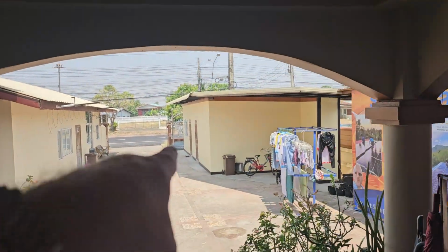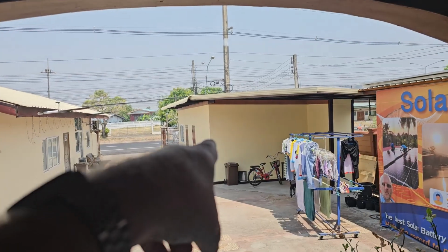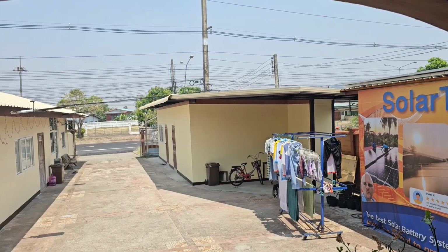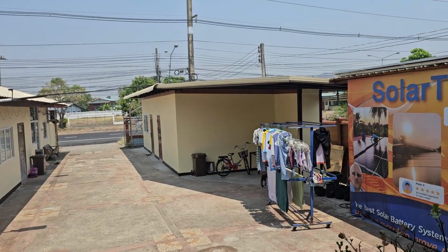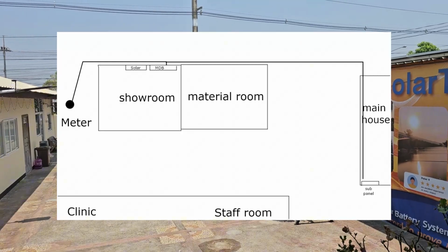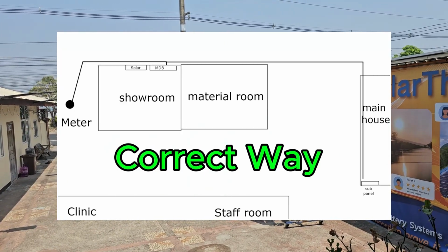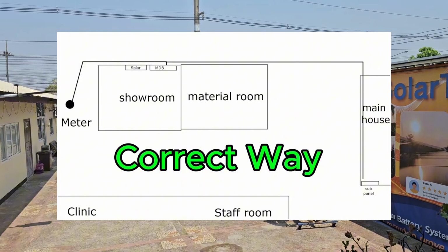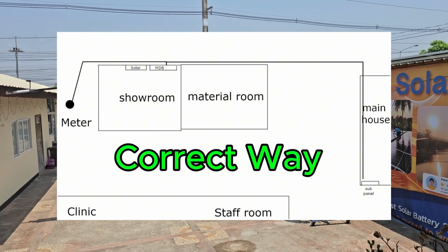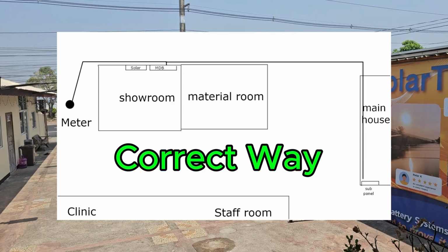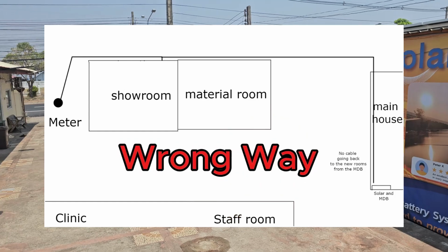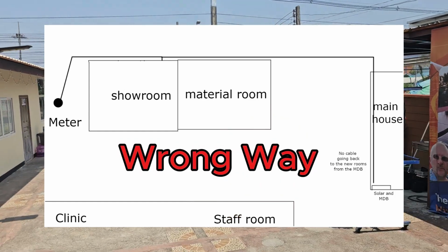have the solar system in the first room and then measure the electricity at that point, which means that it's measuring all the power going into all the rooms, because it's measuring at the first point. That's the whole key. Okay? So I'll show how that works on some drawings, so you can see it in the drawings too. But that is the essence of the main split problem and how to avoid it.